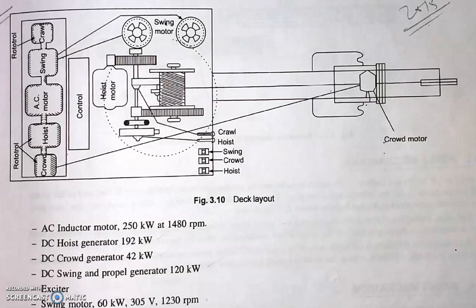There is a common shaft connecting the motor, generator, and exciter. The AC motor is energized by taking power from the HT line, which finally drives all the generators. All the generators are DC generators. The crowd generator supplies power to the crowd motor, the hoist generator to the hoist motor, and the swing generator supplies power to the swing and propel motors.